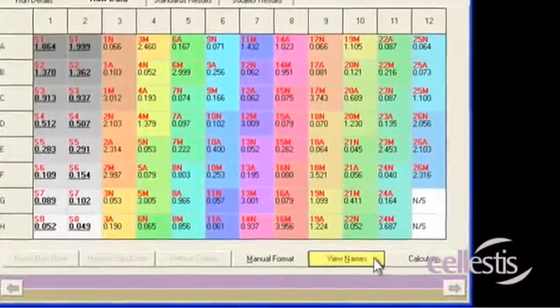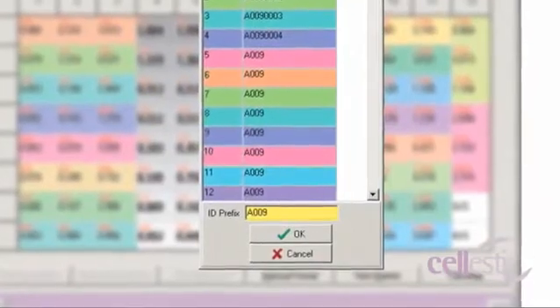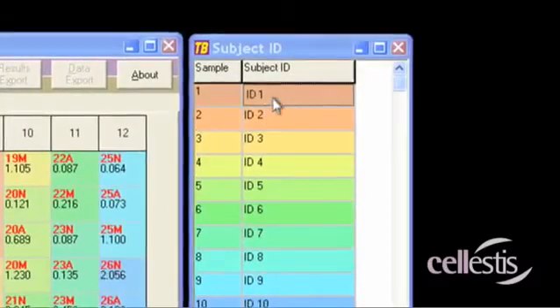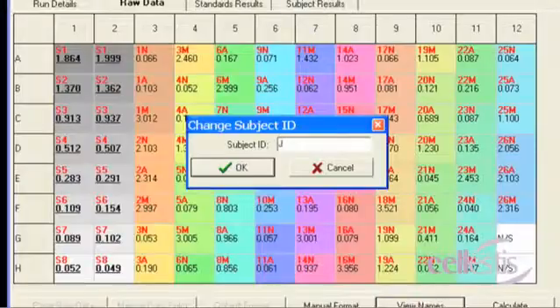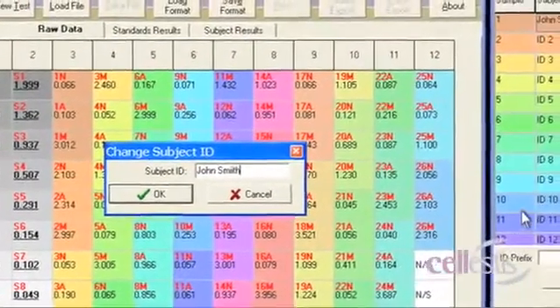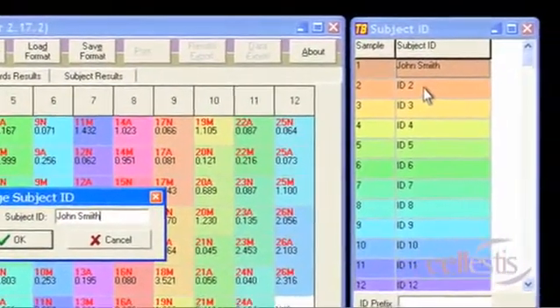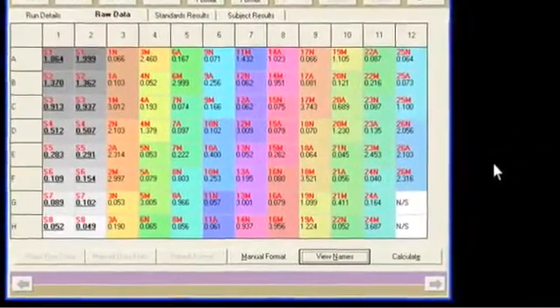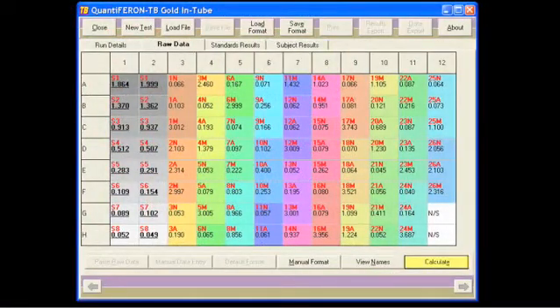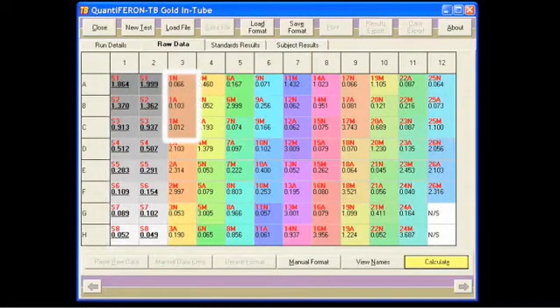The Subject IDs can be added or changed by selecting the View Names button. If all subject IDs are to begin with an identical prefix, these characters can be entered into the Prefix window. In the Subject ID window, double-click on the colored block for each subject and type or scan the new information in the pop-up box. The remainder of the subject's IDs can be added manually by double-clicking or pressing Enter for each subject. Once the correct format has been applied and all subject IDs entered, the next step is to select the Calculate button. In order for the Calculate button to be enabled, at least two blocks of standards and one subject block must be assigned.